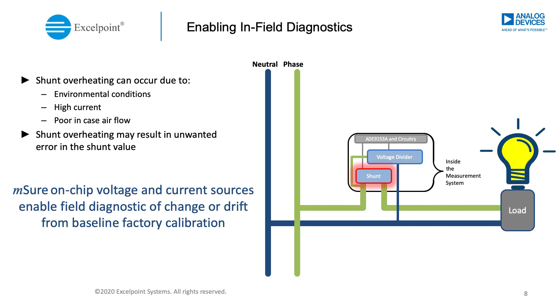With the innovative mSure technology, you can enable field diagnostics and check drift from baseline factory calibration. This helps eliminate the need to send your field application in to calibrate the equipment on the spot, and you can do it over the cloud instead.